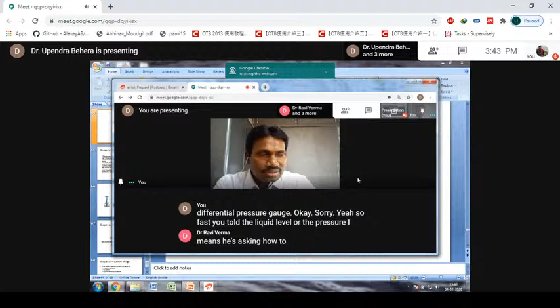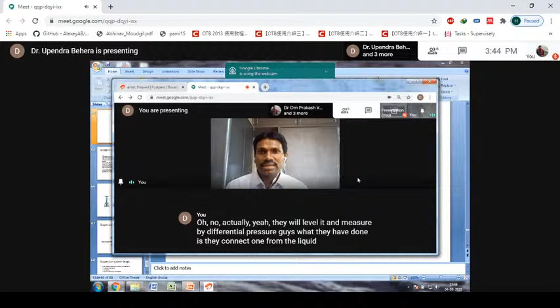No. Actually, level can be measured by a differential pressure gauge. What they do is connect one line from the liquid level, because when there is liquid there will be some pressure - similar to the Bourdon tube, but closed. One line is taken from the vapor space, and the other from the bottom, up to the lowest level of the liquid.